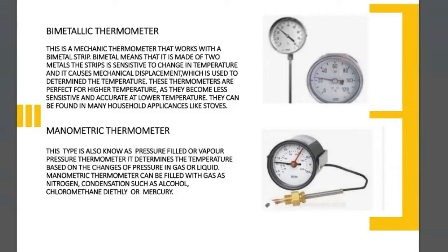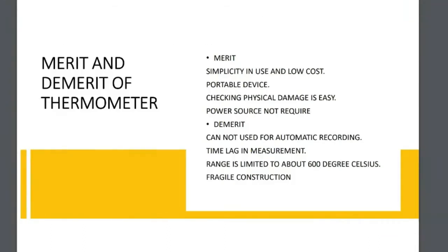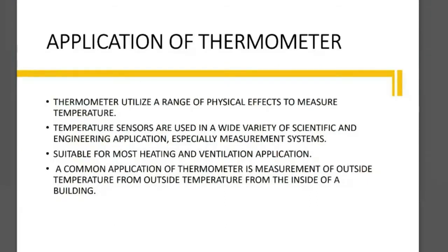Next will be explained the merits and demerits of a thermometer. Merits: simplicity in use and low cost. Portable device. Checking physical damage is easy. Power source not required. Demerits: cannot be used for automatic recording. Time lag in measurement. Range is limited to about 600 degrees Celsius. Fragile construction. Next slide. Application of thermometer.